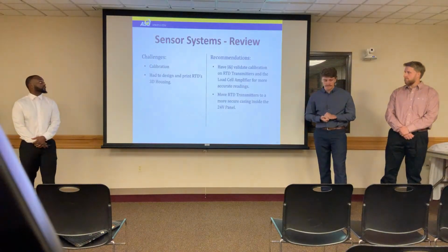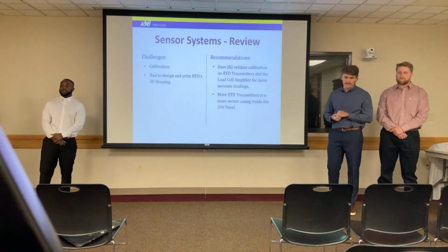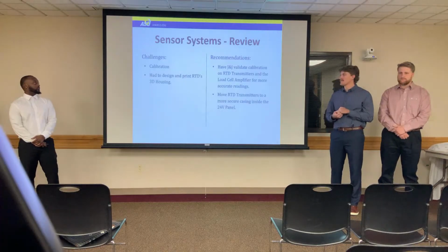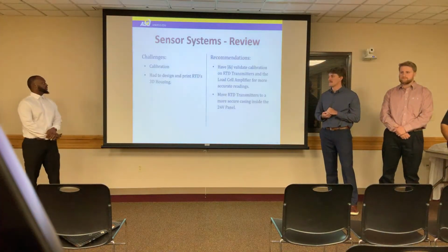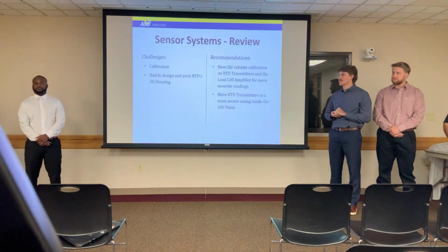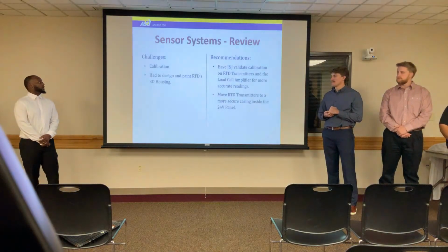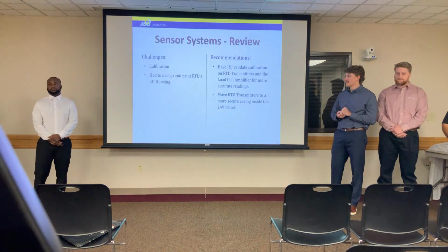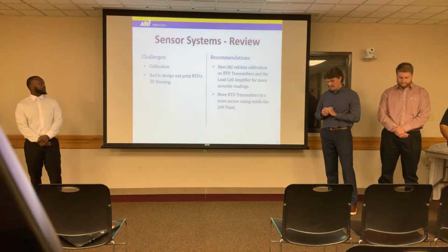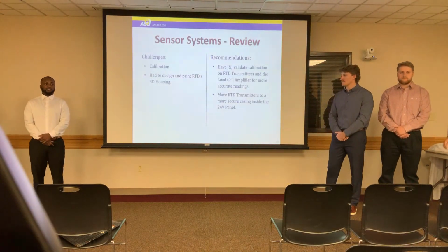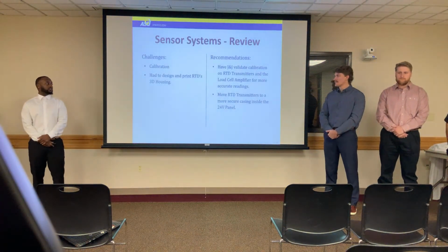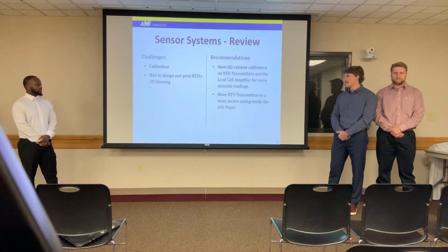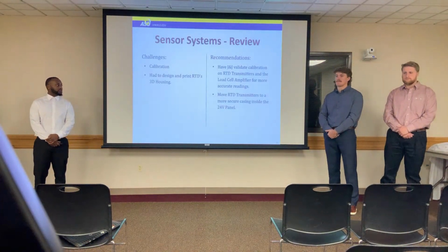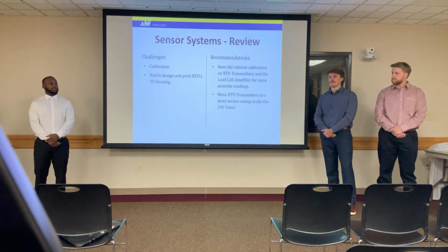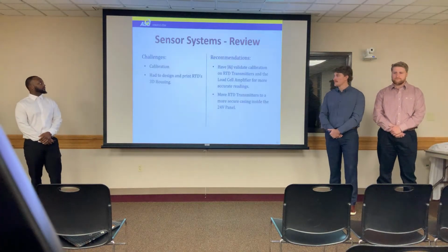Right, and then the challenges for the sensor systems was calibration, because we didn't have any experience with calibrating those. And also we had to design and print the 3D housing for the RTD transmitters. And then our recommendations would be for J&J to validate the calibrations that we already did on the load cell and the transmitters. And then also to maybe move the RTD transmitters into a more secure casing in the 24 volt panel.